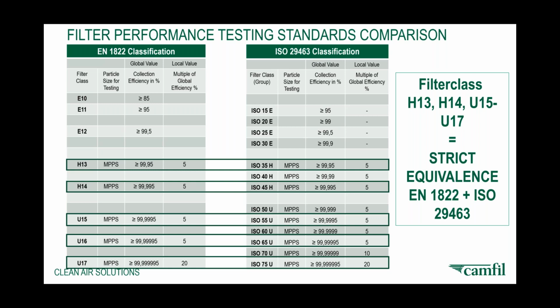And this classifies the filters into, as we discussed, H13, H14, or in ISO 35, ISO 40, ISO 45, etc. Irrespective of how it classifies, if you're looking at the efficiency, in the case of an H14 filter, it is 99.995% at MPPS. So if you're looking at a most penetrating particle size of between 0.1 and 0.2 microns, or a virus of a similar size, that's how efficient a HEPA filter is.